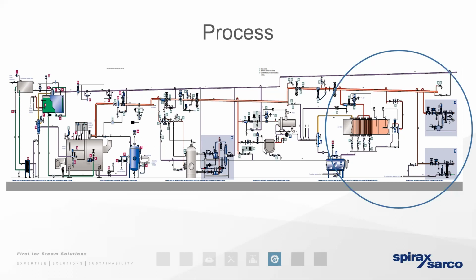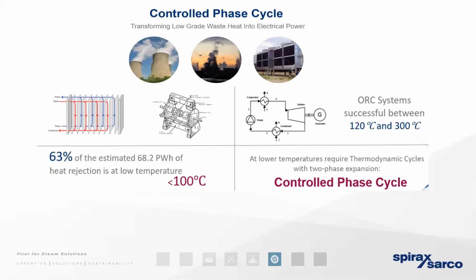And that's where we know that the condensate is going to exist at equally high temperatures and pressures. But it may well be that we've got a source of effluent that exists at an equally high temperature or pressure. So what we need to really do is look at ways that we can not only utilize the steam and the condensate more efficiently, but also utilize the waste heat as well. And that's where one of our products that we call the Controlled Phase Cycle, or the CPC for short, has really got its place. So we know that a lot of industrial processors reject a significant amount of waste heat in the form of effluent.